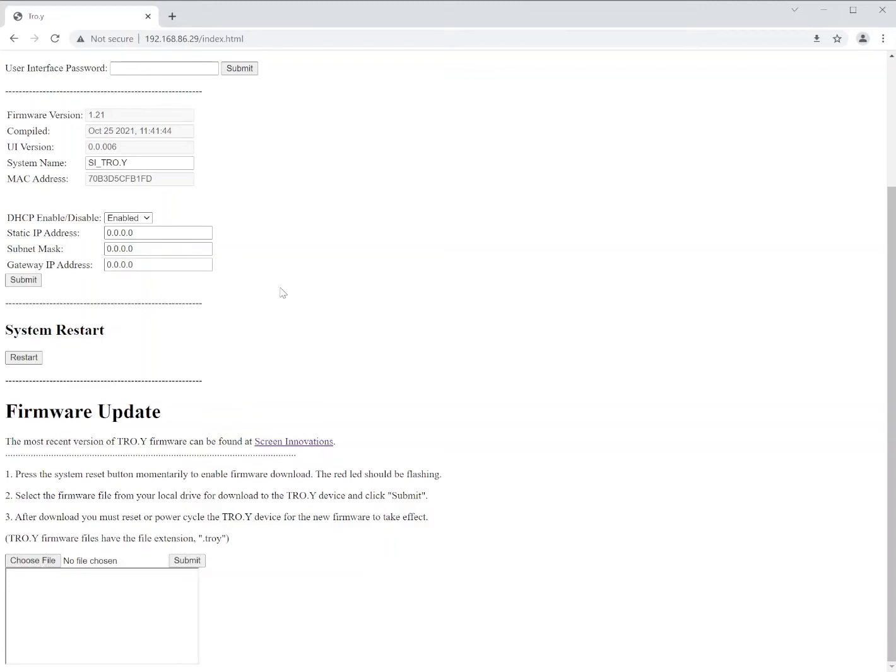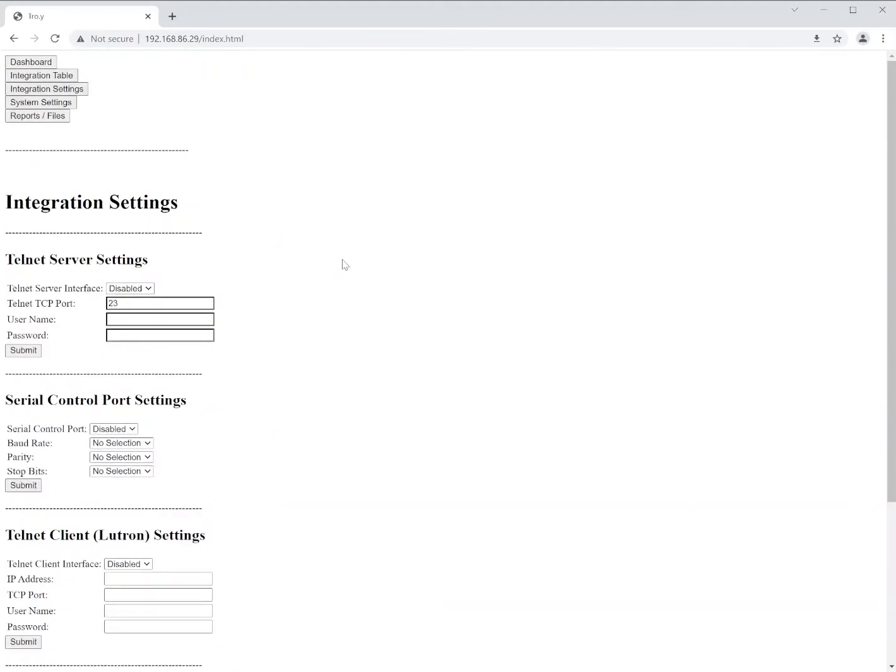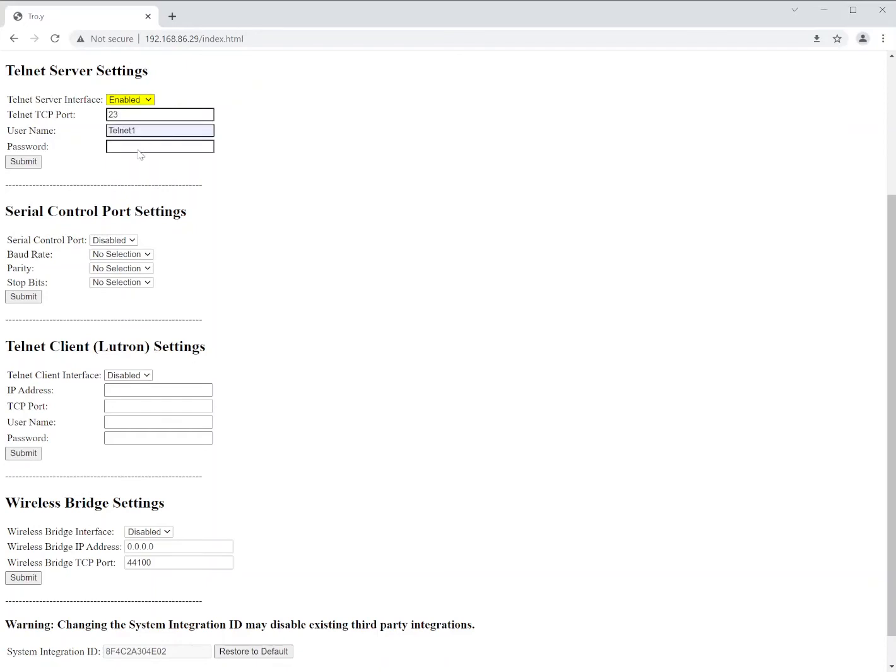After the firmware has been updated, we're going to want to go to the integrations page. We'll start with the integration settings. Here is where we turn on and off the functions we want to use. The Telnet server is the first one we're going to discuss. This is what allows third-party devices to connect to the Troy via Telnet. The port is already set, which is 23 if it's not set. And then we're going to apply a username and password. You don't have to have a username and password, but it is recommended. Once you apply those, you always want to click the Submit after making any changes.